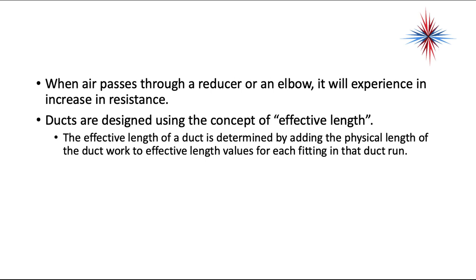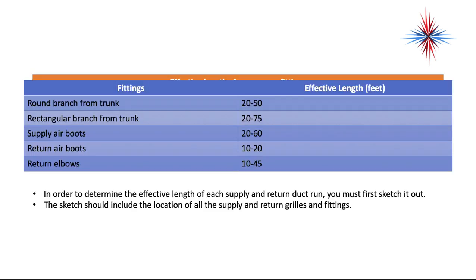Ducts are designed using the concept of effective length. The effective length of a duct is determined by adding the physical length of the ductwork to the effective length values for each fitting in that duct run. Here are some effective length examples: a round branch from a trunk line has an effective length of 20 to 50 feet; supply air boots 20 to 60 feet; return air boots 10 to 20 feet; return elbows 10 to 45 feet, depending on how tight the elbow is.